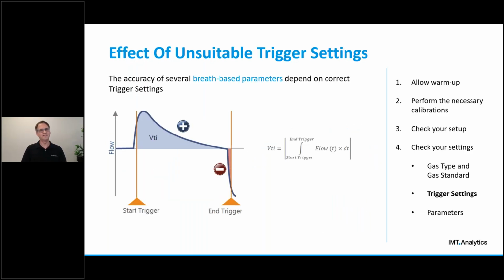So we've just learned that our gas flow analyzer needs to be triggered in order to be able to measure breath-based parameters. But even if your gas flow analyzer is triggering, inappropriately set trigger settings for your specific application can have significant impact, for example, on tidal volume accuracy.